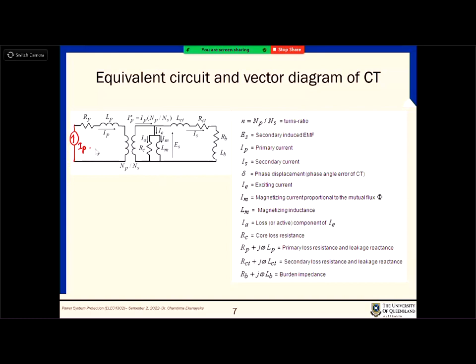So you have a 100 MVA system where hundreds of amps are going through the conductors. You have a CT, and then you make a mistake in the secondary circuit. Do you think that will change the amount of power going through the transmission line? 100 MVA? Nah, right? So it will affect the CT. CT could, probably, go into saturation or whatever, different things could happen, right? But it won't affect the primary current, right?